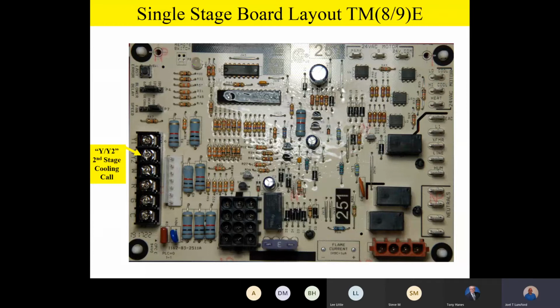No, that's not correct. The Y1 input is strictly for a two-stage product, first stage airflow, and then the Y/Y2 is second stage airflow on a two-stage product, or that's the terminal you use if you have a single stage product outside, because if you think about it, you want 100% airflow on a single stage product outside. Is there any questions or comments on that?